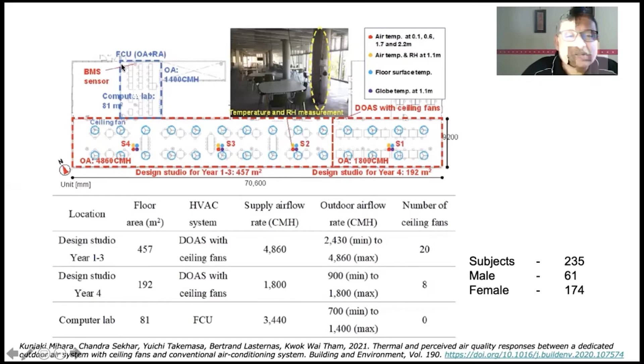There are two parts here. The red block is the design studio, which has the hybrid concept—DOAS and ceiling fan combined. Then there's a conventional computer lab setting with the conventional FCU air conditioning system. So we are comparing the typical conventional air conditioning system space, served at 24 degrees, with the design studio served by the hybrid DOAS and ceiling fan system at 27 degrees and elevated airspeed.